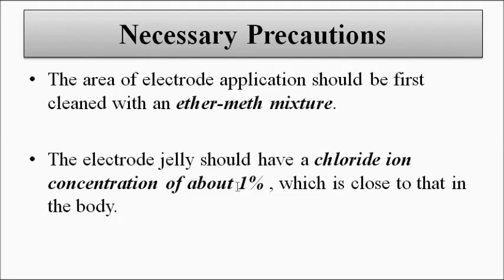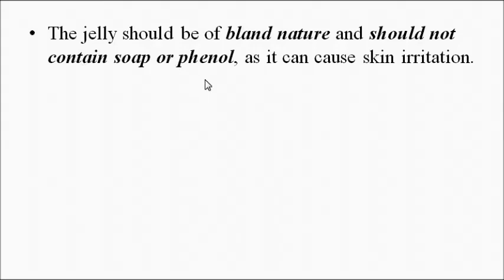Another important thing is that the jelly or cream should have a chloride ion (Cl⁻) concentration of about one percent. The electrolyte or electrode jelly should have a chloride ion concentration close to that in the body, since the human body is composed of various electrolytes — positive and negative ions, such as Na⁺, K⁺, sodium, potassium, and chloride. Additionally, the jelly should be of a bland nature and should not contain soap or phenol, which can cause skin irritation.